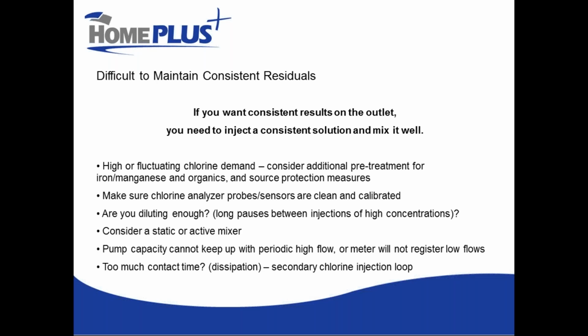It's going to be inconsistent if you haven't run it through some pipe or through a static mixer or into your contact tank. But if it's still inconsistent after your contact tanks, that's where you really have a significant problem that you want to address, related to either your chlorine demand, your dilution, etc., or dissipation. You've just got too much contact. Basically, we can't expect consistent results on the outlet if we don't have consistent results on the inlet. A consistent solution mixed well, and consistent chlorine demand.